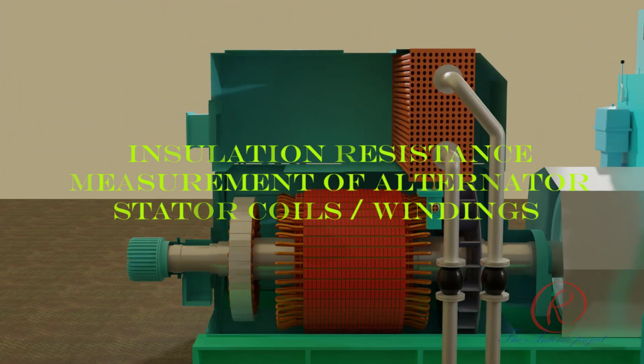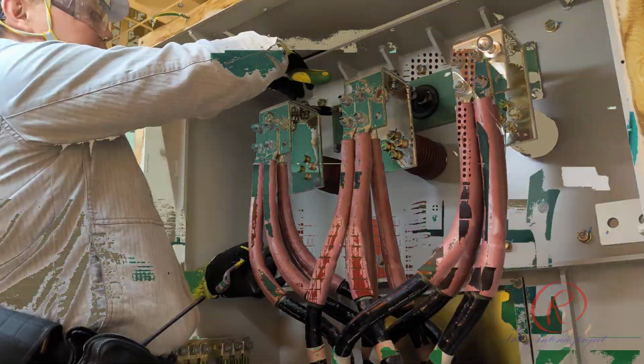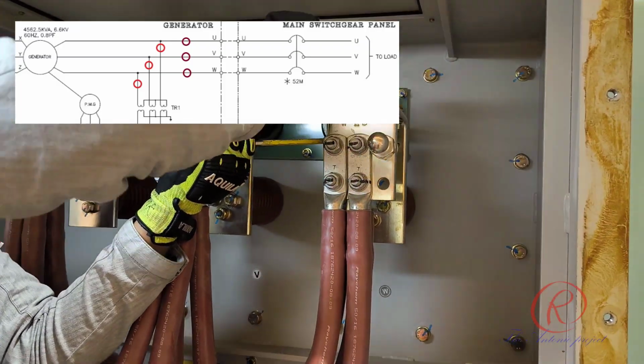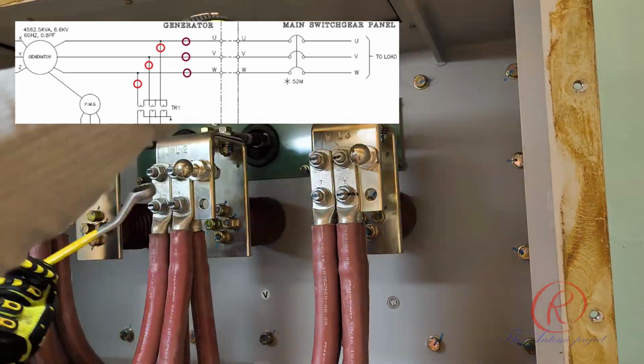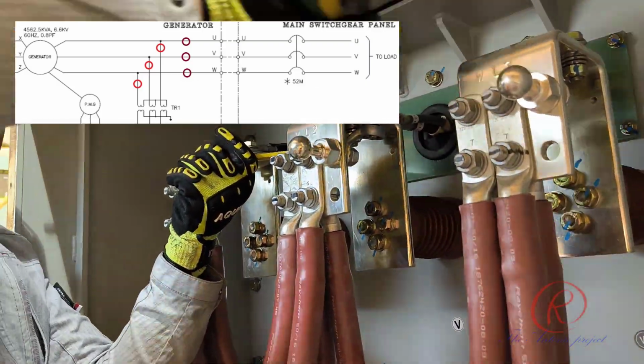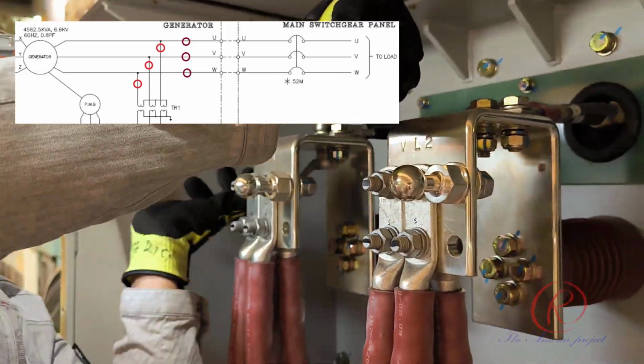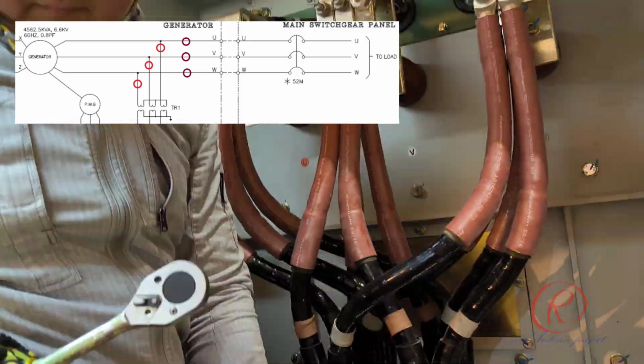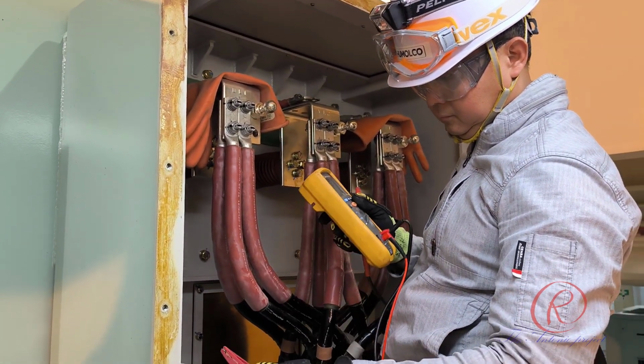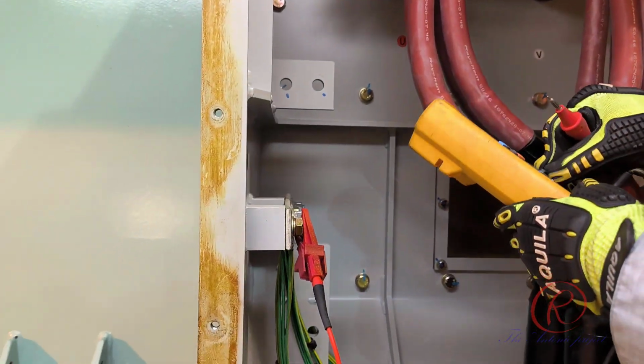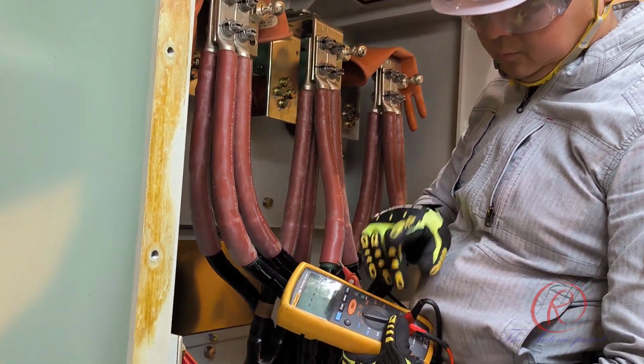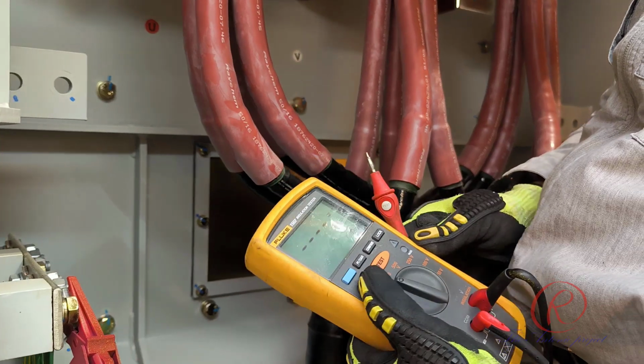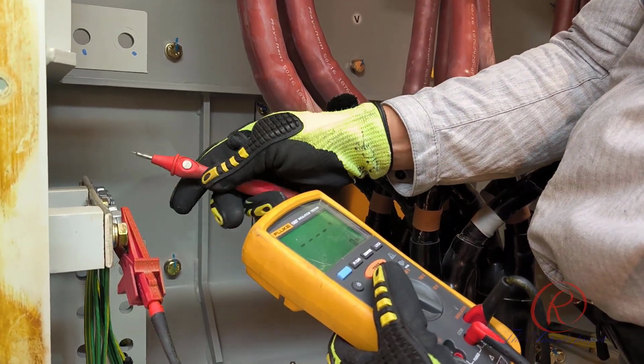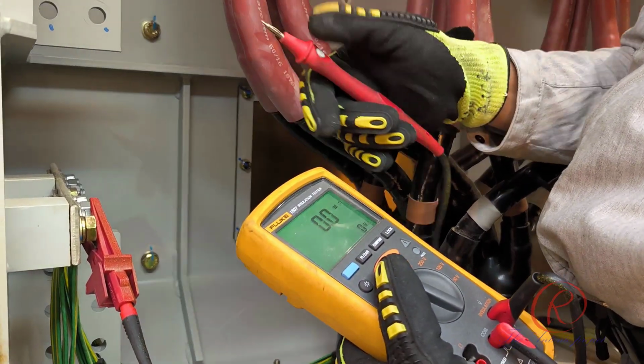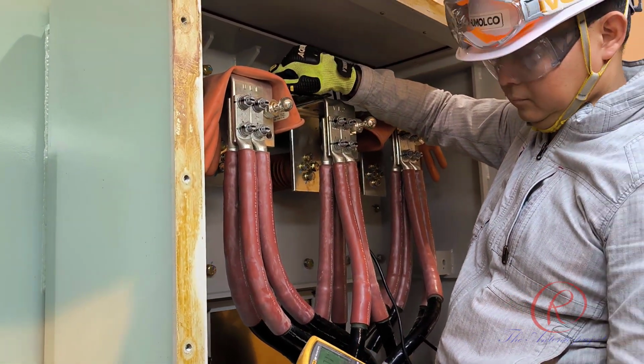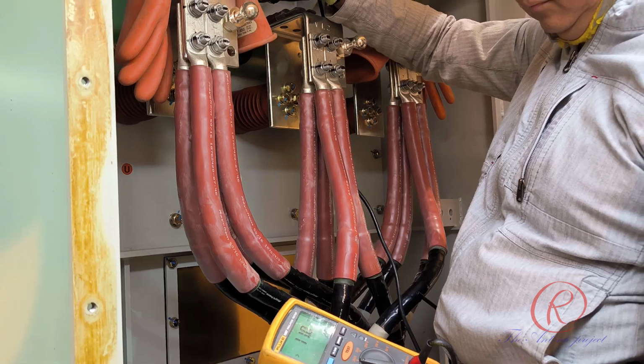Insulation resistance measurement of alternator stator coils or windings. In order to get a correct insulation resistance measurement result, disconnect all cables from the alternator terminals. There are two cables from the alternator on each terminal, U, V, and W. One cable is from the stator windings, another cable is for the voltage sensing transformer. As per maker instruction, the required test voltage is 1000 volt DC. Therefore, the megger is suitable for this measurement. Measure the insulation resistance of the windings and take the data. Before carrying out the measurement, short both measurement probes together and press the test button. When the value shows 0 ohm, it means that this measurement instrument is working properly.